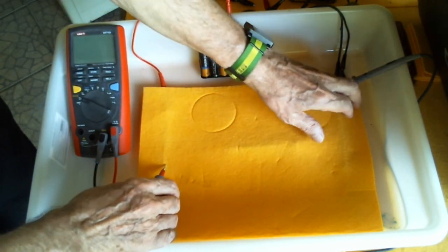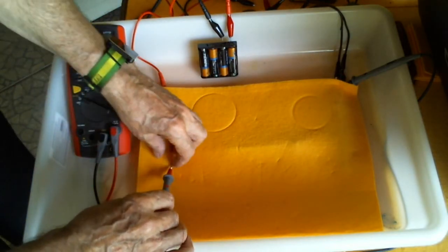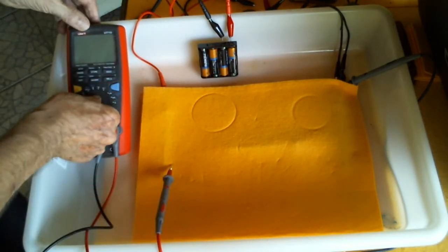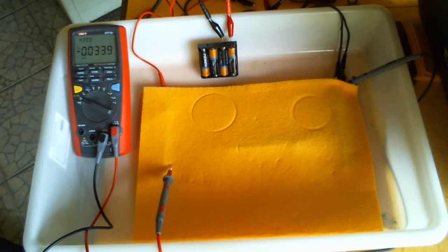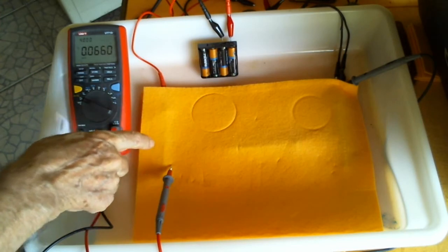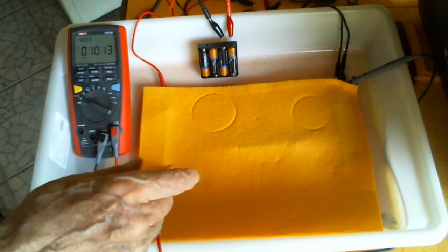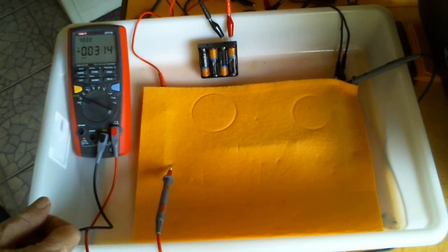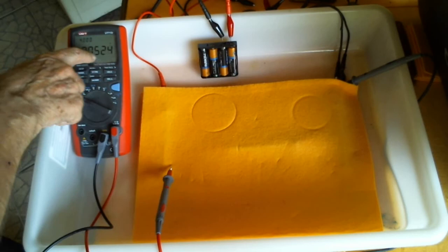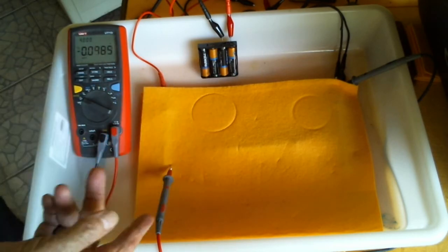I have connected the, reset this. This is dry. Now, we often get dry circumstances on pipeline surveys, and that is, we get no reading because the connection between the meter and the measuring circuit has got so much resistance that the readings on the meter are fluctuating. They are meaningless.